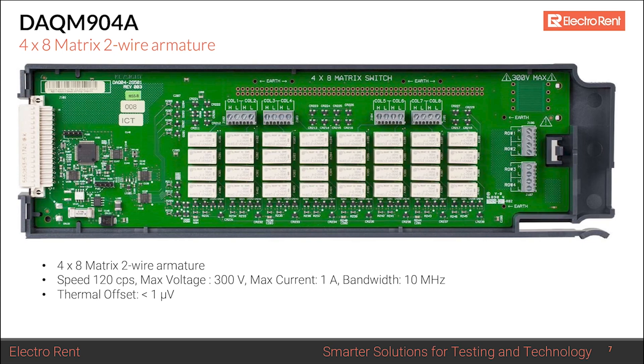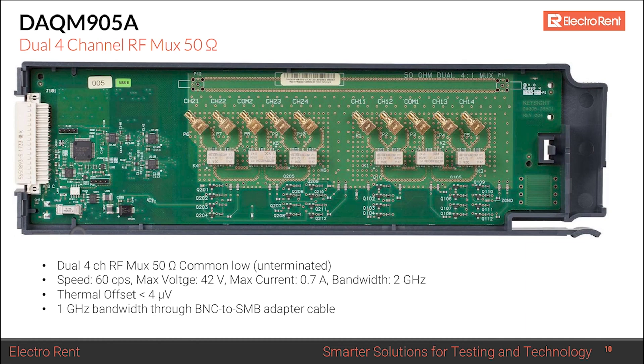The DAQM905A is a dual four-channel RF multiplexer for RF switching. Each of the two channels can be multiplexed to four different destinations. It's 50 ohms with a bandwidth of 2 GHz, suitable for most low-level RF signals. However, this card does not come in 75 ohms, so for 75-ohm applications you may need to go back to the 34972 or the larger 34980, which supports 75-ohm RF switching.